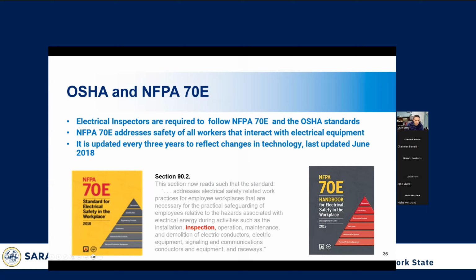NFPA 70E has traditionally been for electrical workers, but now that's been updated to include inspections as well. So inspectors do have to comply with the standard. And so this requires an initial risk assessment. That's thinking about things like whether the electrical inspection will involve removing covers of energized equipment, and that will determine if you need to bring personal protective equipment, PPE, with you, or things like that.